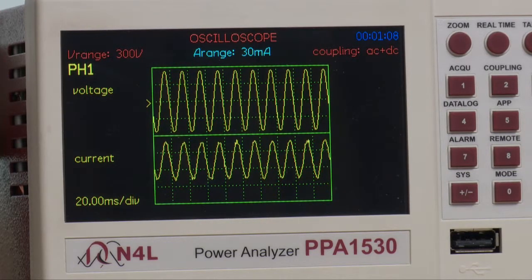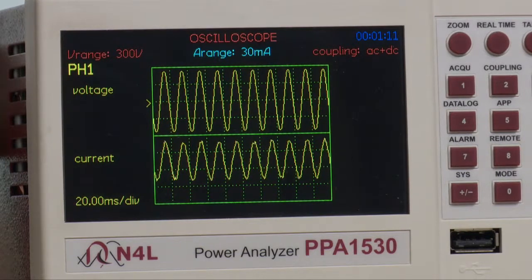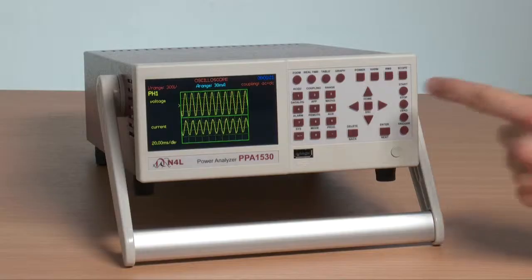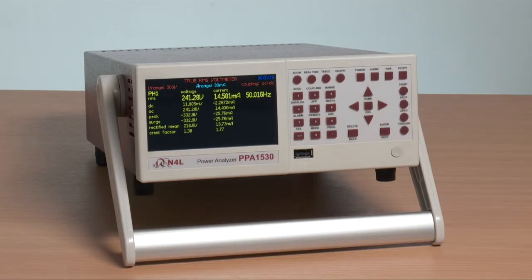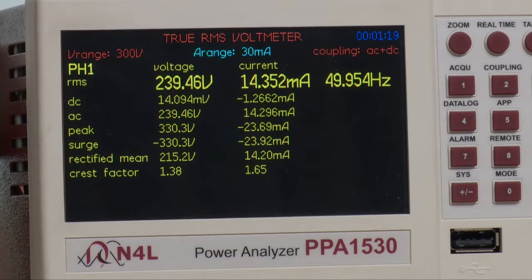If, however, we want to look at harmonics and distortion, we move on to look into different modes. There is an RMS button, which will show all the RMS components, plus the DC, AC, peak, surge, rectified mean, and crest factor of voltage plus current and frequency.